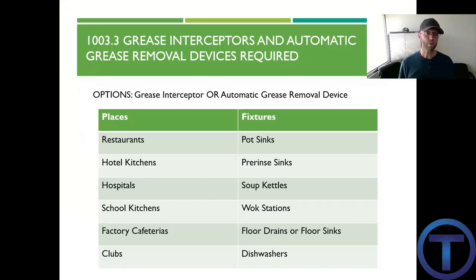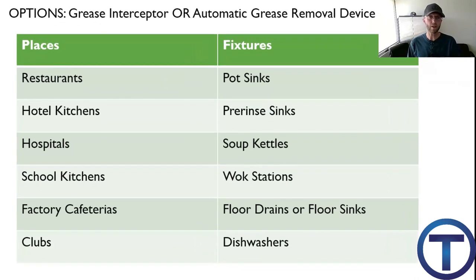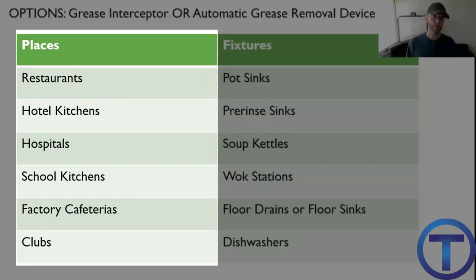Just a quick caution: if you're ever involved with servicing an operational grease interceptor like this, you need to understand that these are rancid and it will likely ruin your lunch. Section 1003.3.1 talks about grease interceptors and automatic grease removal devices, stating these are required — but you have those two options. Some of the places you'd be required to install them include restaurants, hotel kitchens, hospitals, school kitchens, cafeterias, and clubs — places where you mass produce food and there's a lot of food waste and dishes.